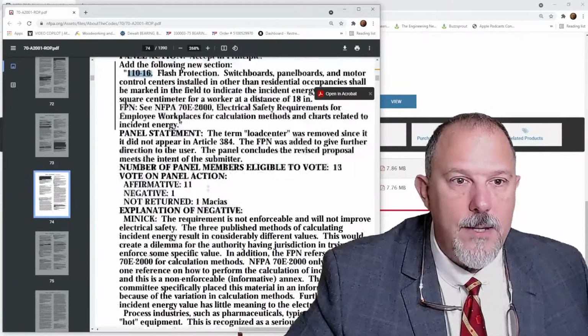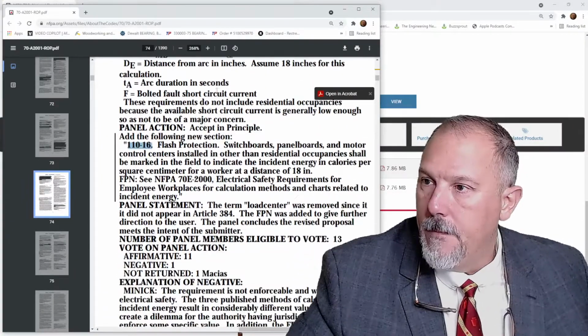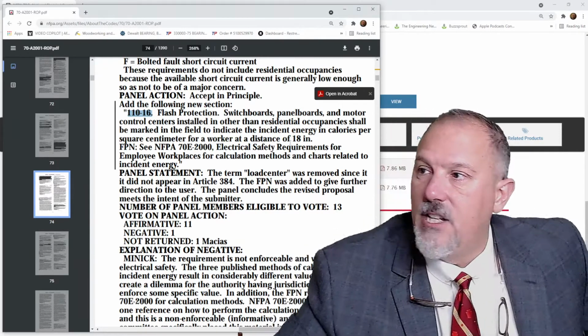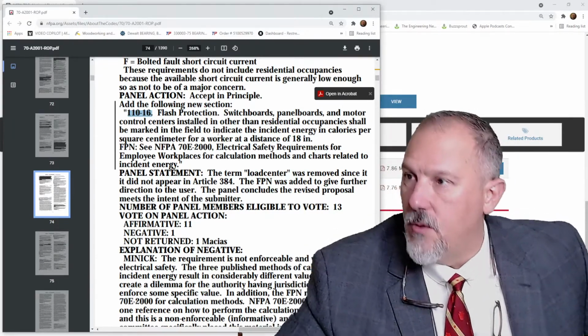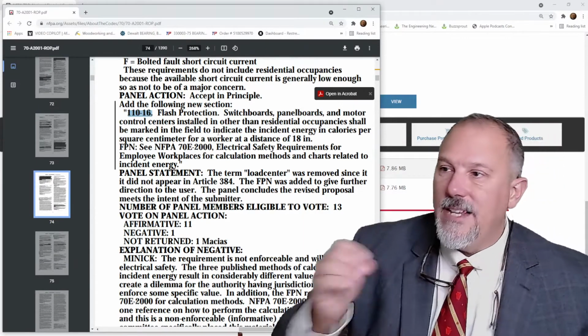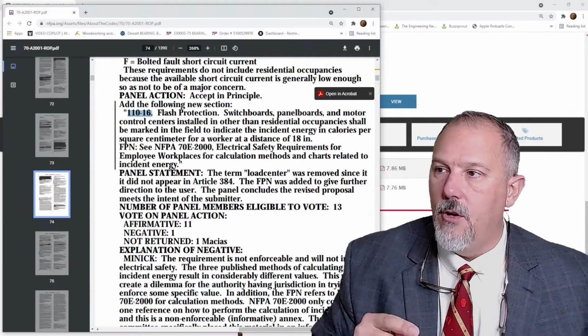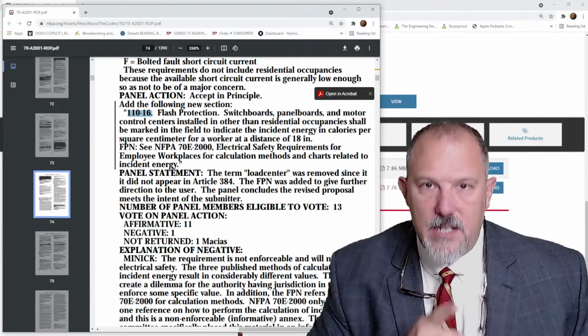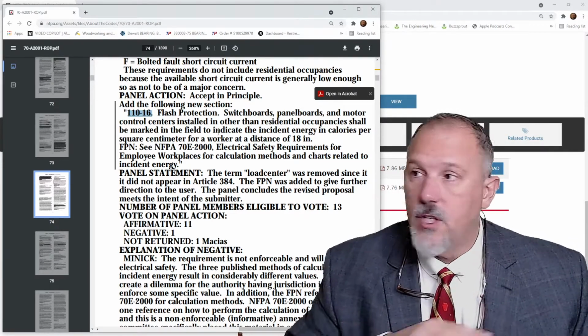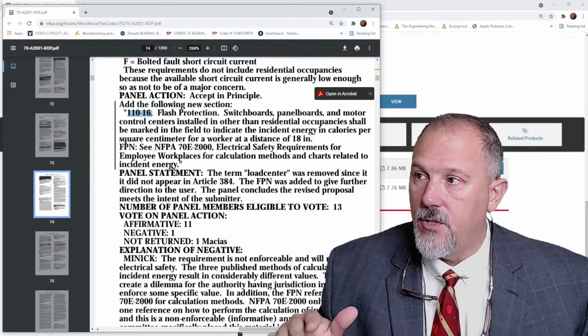Let me show you something. Let's take a look at what the panel agreed to. The panel action was accept in principle 110.16: switchboards, panel boards, and motor control centers installed in other than residential occupancies shall be marked in the field to indicate the incident energy in calories per square centimeter for a worker at a distance of 18 inches. This would have been all switchboards, all panel boards, and motor control centers in other than residential occupancies.